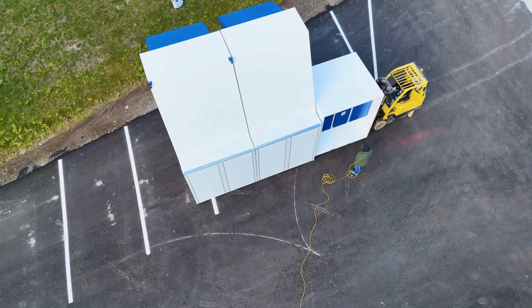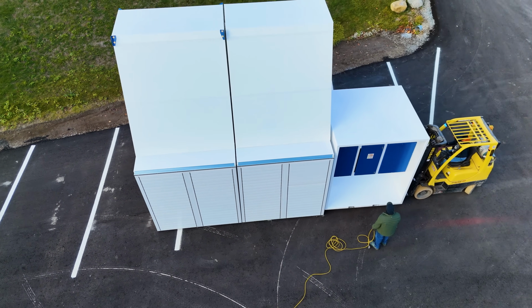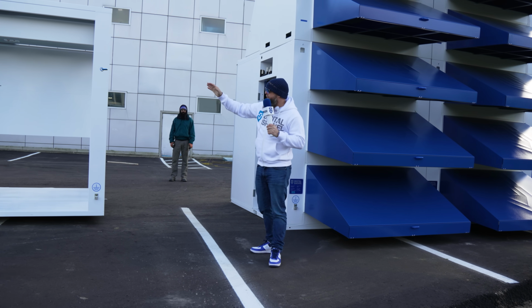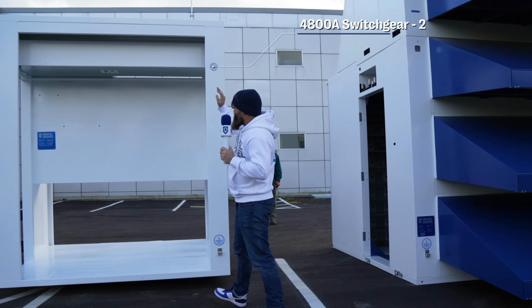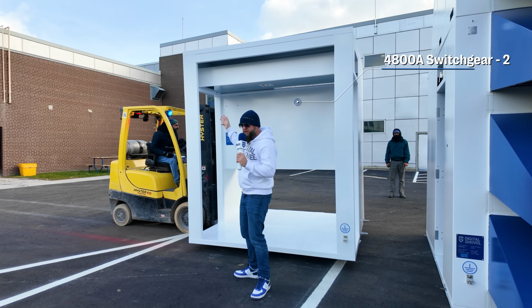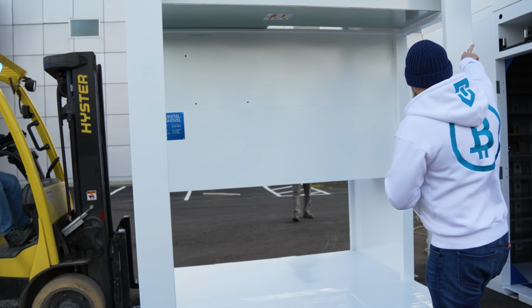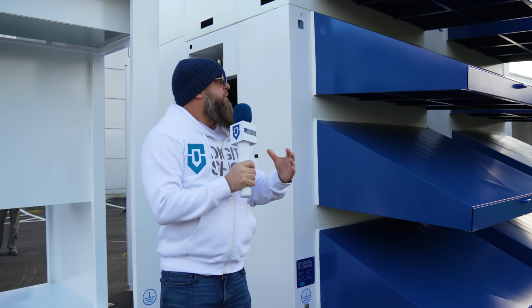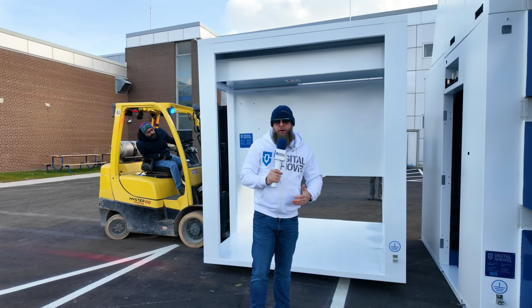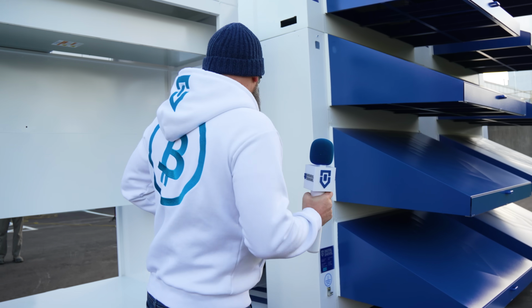All right, so what we've got here is our 4,800 amp switchgear. This is gonna go into the middle, our overhead busway system that we have in here. We've got 2 1,200 amp buses going each direction. 2 going that way, 2 going this way, and that can distribute up to 4,800 amps or 3 megawatts of power across the Digital Shovel Bitcoin mining strings. We've got our 2 1 megawatt string set up of the new Digital Shovel Gen 3 Bitcoin mining farm.